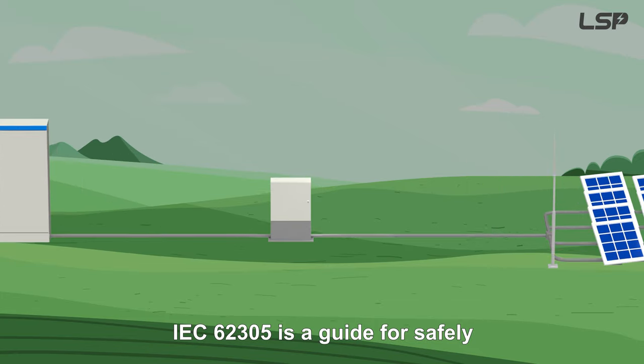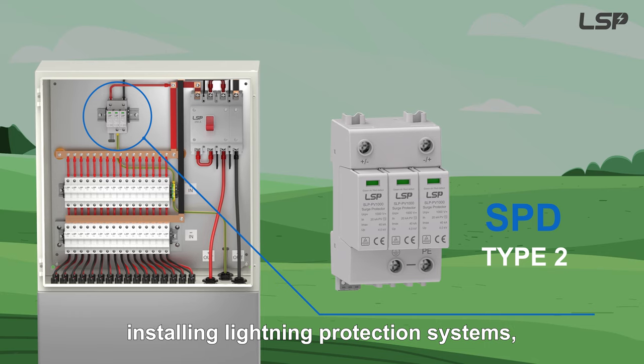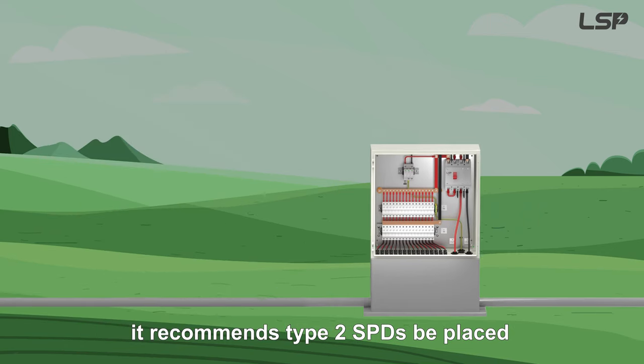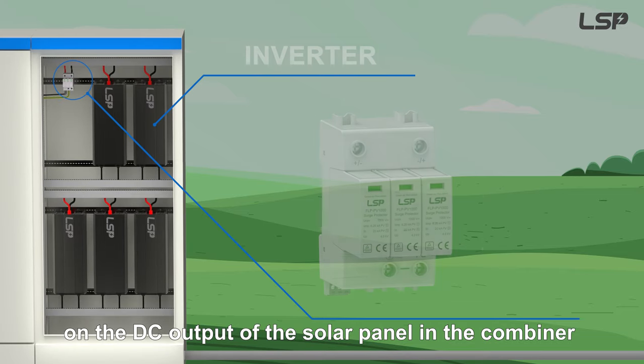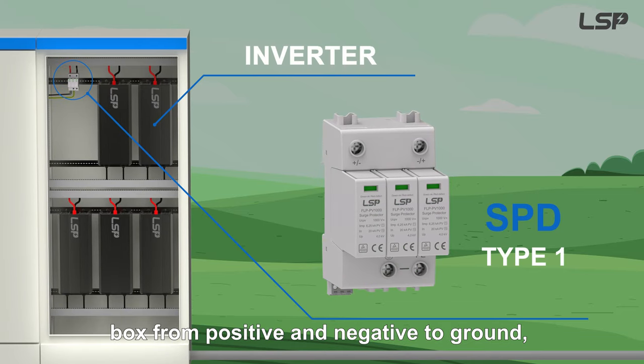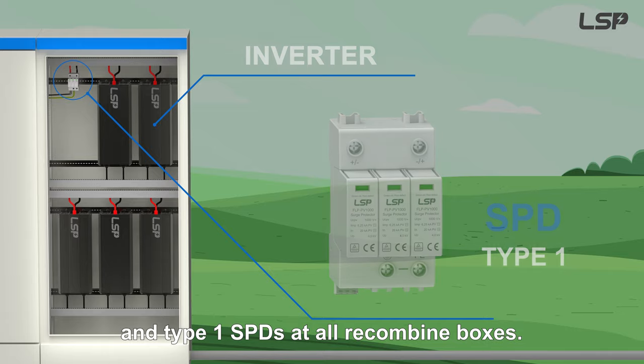IEC 62305 is a guide for safely installing lightning protection systems. It recommends Type 2 SPDs be placed on the DC output of the solar panel in the combiner box, from positive and negative to ground, and Type 1 SPDs at all recombiner boxes.